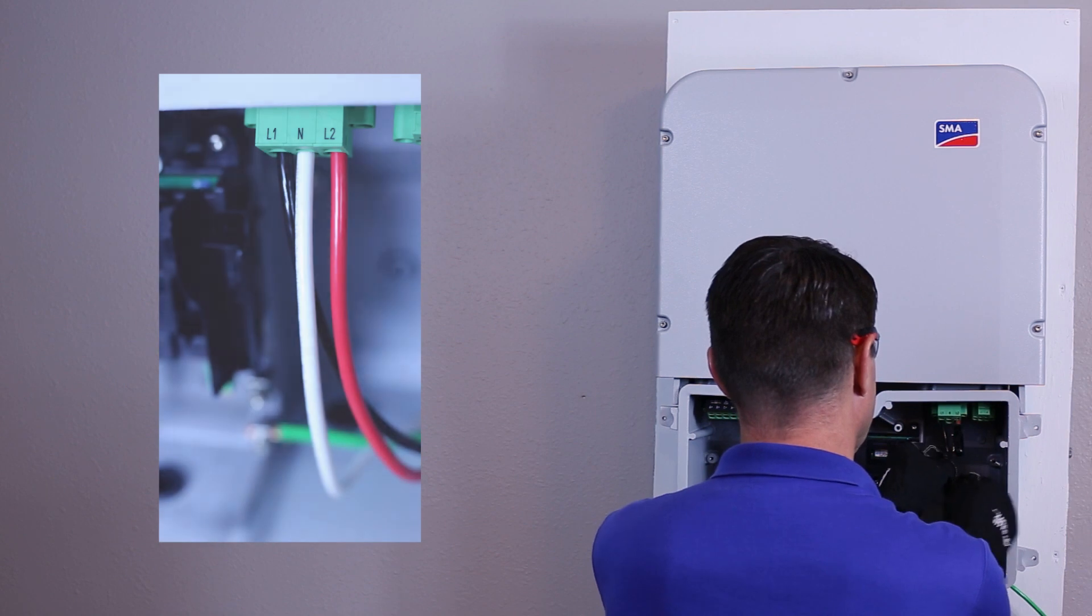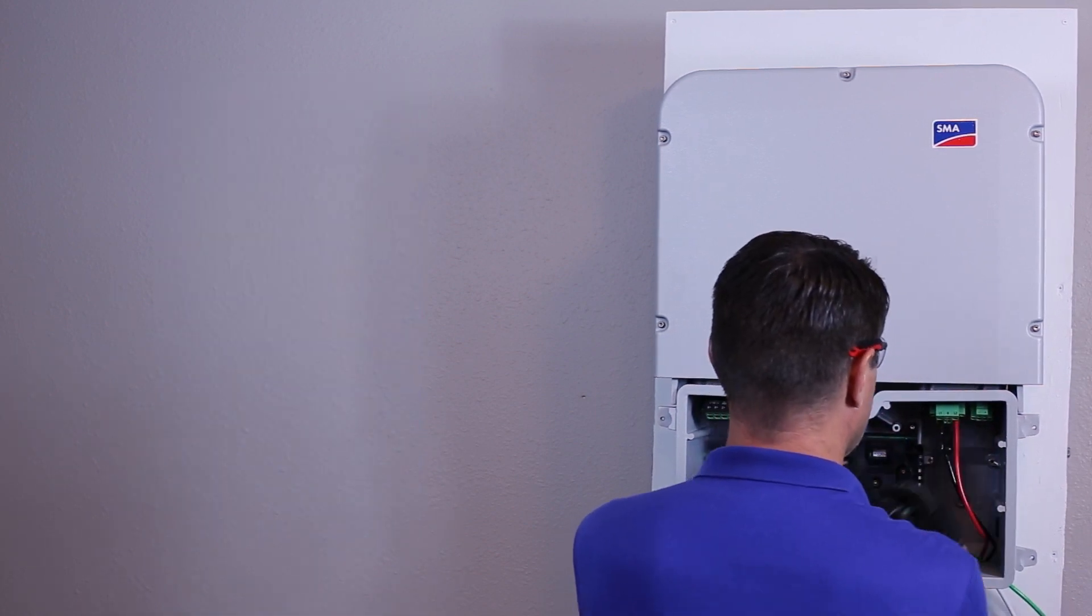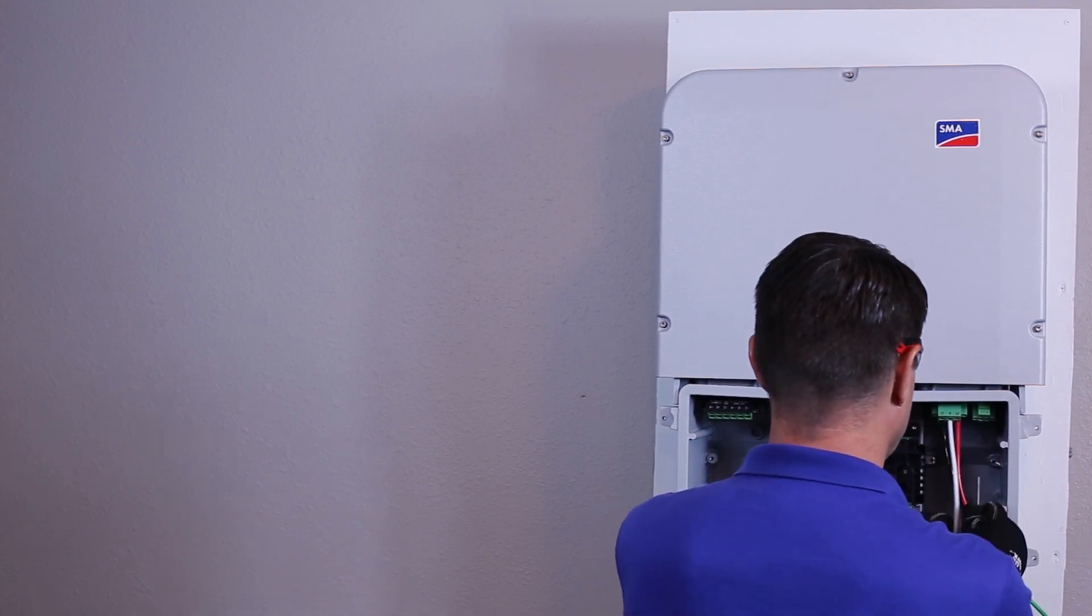Insert AC line 1 and line 2 conductors and, if appropriate, neutral. If installing line to line on a 208 volt or 240 volt delta service, remember to select the correct grid code during commissioning.